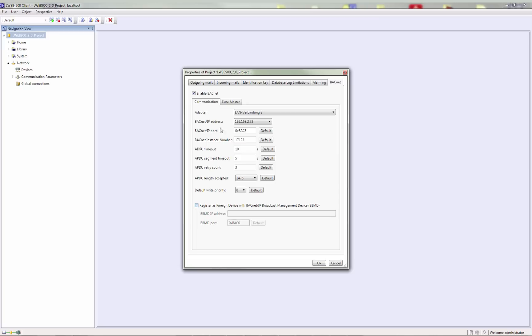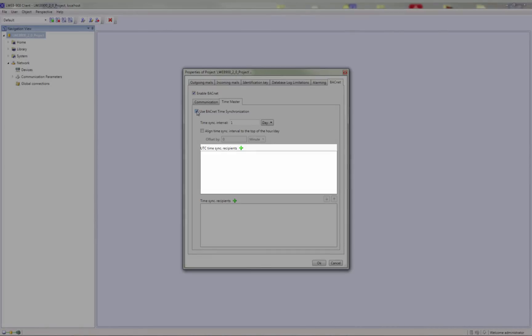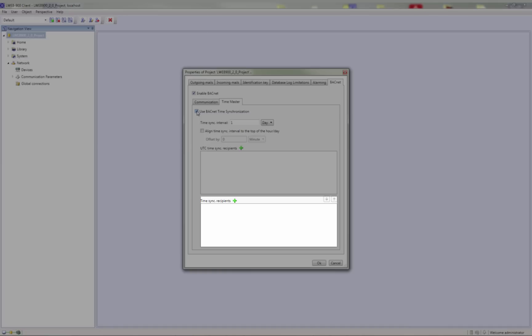The LWEB900 server can serve as a BACnet time master. Enable the Use BACnet Time Synchronization checkbox and set a synchronization interval. You can add BACnet devices which should receive UTC time and devices which should receive local time.